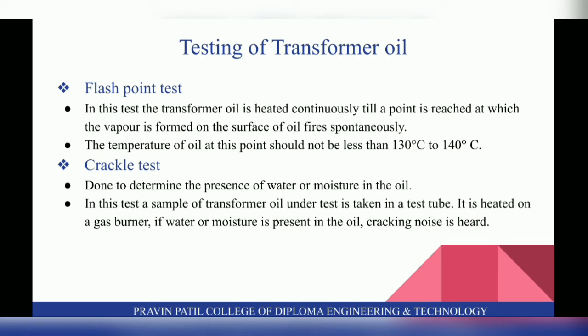The objective of this test is to determine the presence of water or moisture in the oil. In this test, a sample of transformer oil under test is taken in a test tube. It is heated on a gas burner. If water or moisture is present in the oil, a cracking noise is heard.